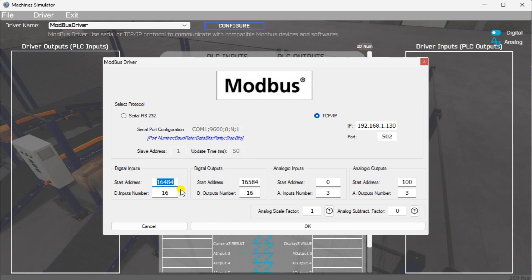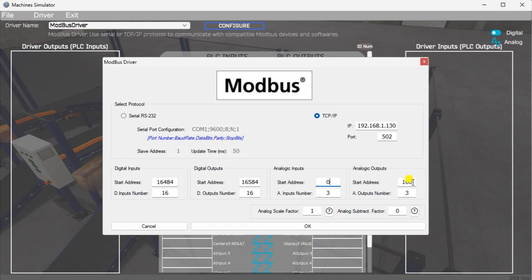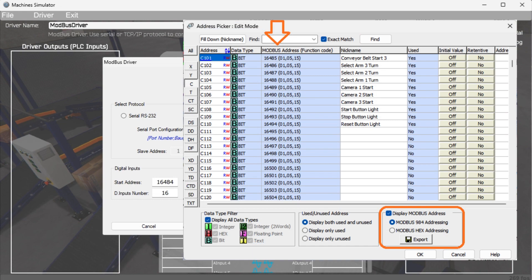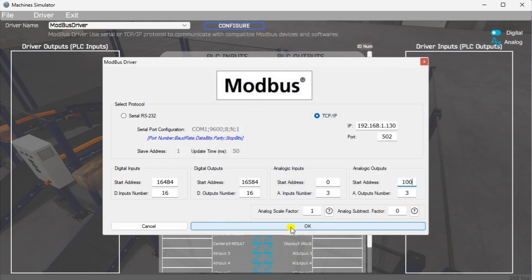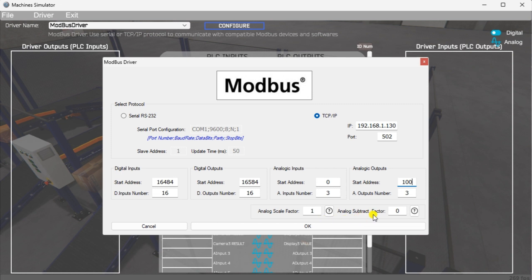Digital inputs from MS to the Click PLC will start at C101. This will start at address 16484 due to the offset of 1. Digital outputs from MS to the Click PLC will start at C201. This will begin at address 16584 due to the offset of 1. Analog inputs DS1 will start at address 0. And address DS101 will begin at address 100. This is due to the offset of 1. The address picker in the Click programming software will help determine the Modbus address. The analog scale value is 1. This is used to divide and multiply so that the Modbus analog value can be read and written within the simulator. The analog subtract factor is 0. This is used with the analog to obtain negative values within the Modbus analog registers.